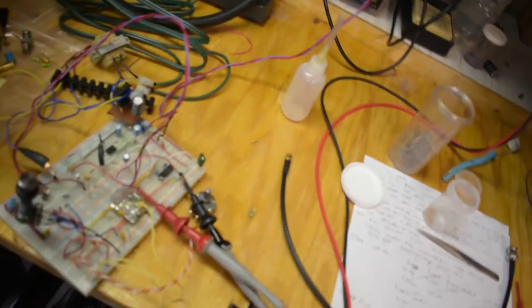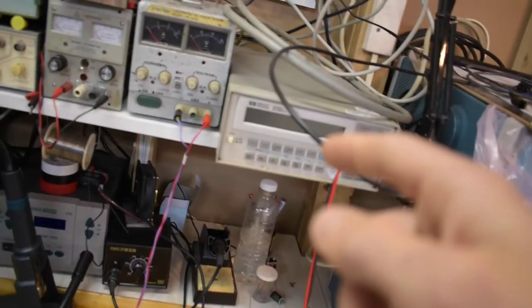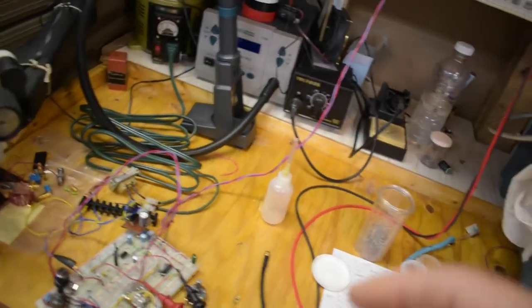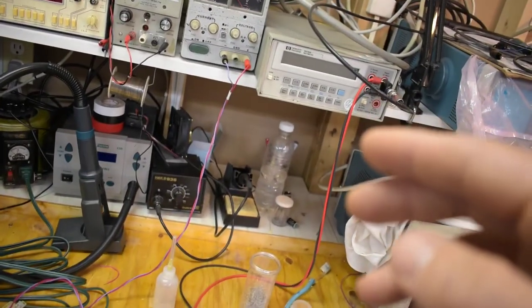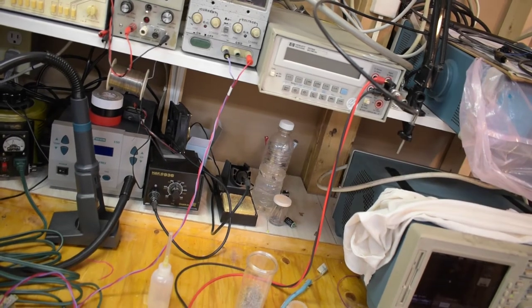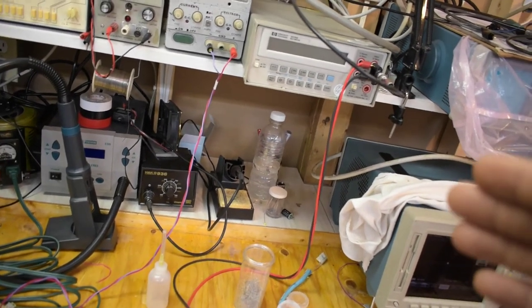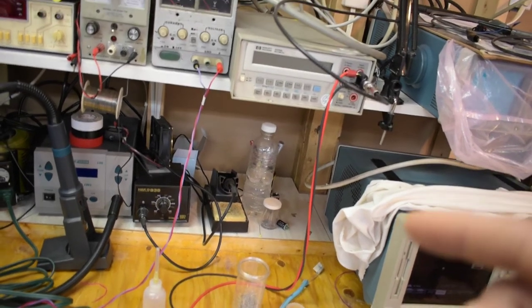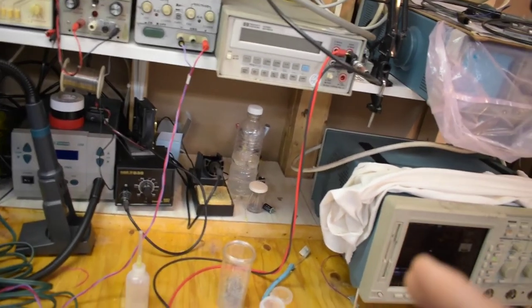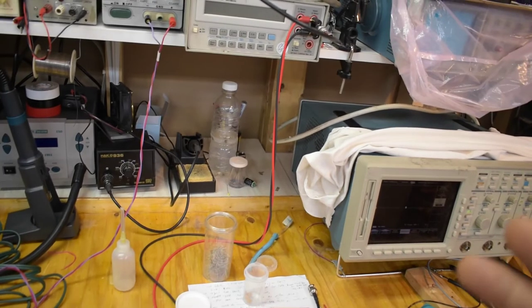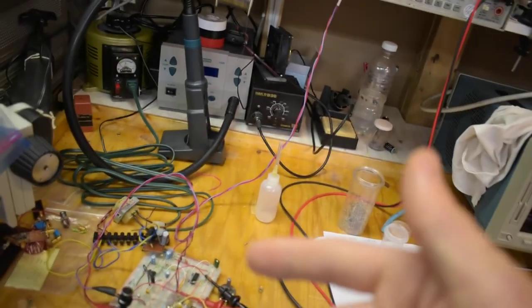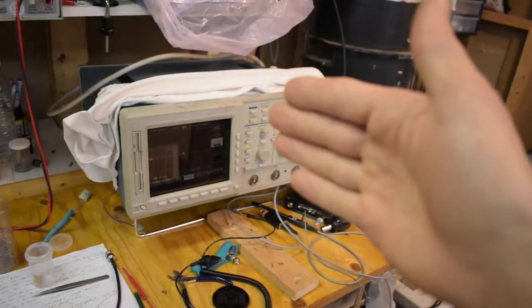So it's just a manual feedback loop where I twiddle these knobs and look at the readings there, and it's actually pretty decent. I've let this warm up a bit, and I can set it to 9.5 volts, so 9.500 something. And the last digit, so less than a millivolt, it'll drift around a bit, but it's still very good. And it doesn't need to be stable for 10 hours straight. It just needs about 20 seconds per setting, maybe 30 seconds, I'm not sure. So you set it to 9.5 volts, make sure it's good, and you just go back here and say, okay, press enter, then it does its thing, and says, okay, change it to -9.5. So then I flip the leads around, just make sure it's still good, and continue.